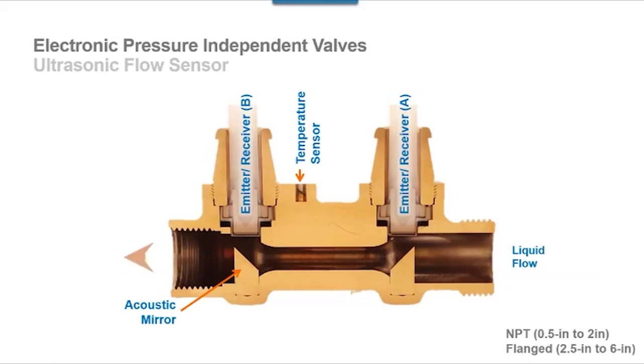On top of it, with the flow meter, unless dirt was an issue, which it's not with the ultrasonic transit time technology, and we're not using a turbine for this, what's the one variable that can change? The fluid. If you're using glycol, we all know that glycol isn't the same from the day the job started as it goes down the line. So this takes care of that one variable that's out there with using ultrasonic flow meters. So using transit time, the flow is calculated.